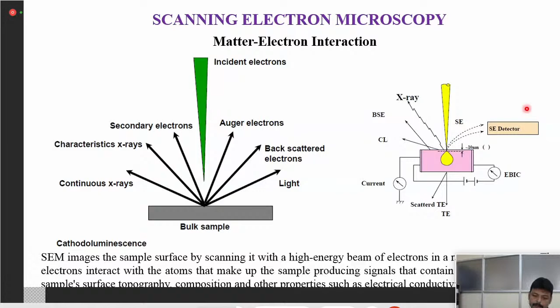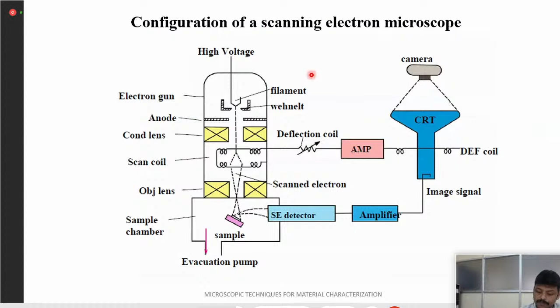So this is the configuration of a scanning electron microscope. The high voltage will be applied to a filament, and there is a cathode-anode system that will be generating the electrons. Different types of SEMs are there. I will discuss different aspects of each point. The first is the electron gun, and then we go to the condenser lens and objective lens. In between, the scanning coils will be there, and inside the sample chamber we will be placing the sample. The electrons come as a straight line and fall on the sample, and we detect the signals using different types of detectors, and they are amplified and converted into images.